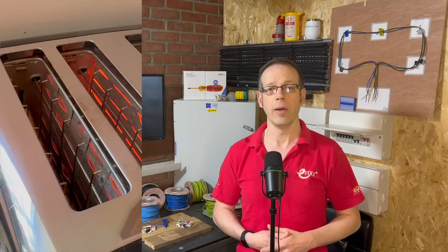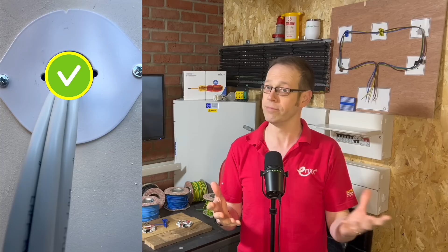A fire protection product we loved here at eFix is the clever Speedcutter. If you missed our previous mentions, it's a drill attachment whose HoleCutter includes an integral fire collar. After drilling, you slot the collar into the hole to maintain the fire protection. In the event of a fire, it will expand and close off the hole, so there's no need for intumescent mastic to be applied after you run the cables through. Told you it was clever. The Speedcutter has classification for EI30, meaning it can be used in any 30-minute firewall if it has a 70mm stud and a layer of 12.5mm board on each side.